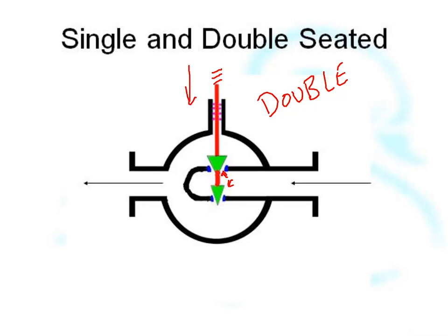Well, sorry, firstly you close the actuator fully, so you push the actuator all the way down fully. And then you rotate the stem until it just pushes back a little bit. And then when it just pushes back a little bit, you know that it's seated. Now what you're supposed to do is get in and adjust only one of the seats. One will be seated at this point, because you can't have it seated on both the seats. So you're supposed to get in and adjust the other seat until it's tight on both seats, but you can never get it tight on two seats.